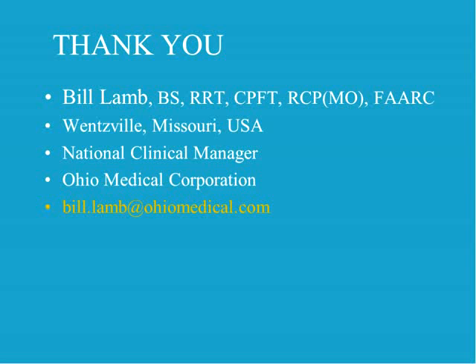That's a loaded question. It depends on the ventilator and the algorithm that they use. My understanding of the literature is that all of the ventilators are doing an estimate of compliance, and that estimate is used for the ventilator's logic if you're doing something like volume control plus or PRVC, or with the Hamilton ventilator if you're doing adaptive support ventilation. It's a good enough estimate to look at relatively one patient versus the other. So in other words, I wouldn't take compliance measurements to compare patients A, B, and C, but I would use compliance measurements to say what was patient A's compliance now versus what intervention did I do, and now what is compliance of patient A.